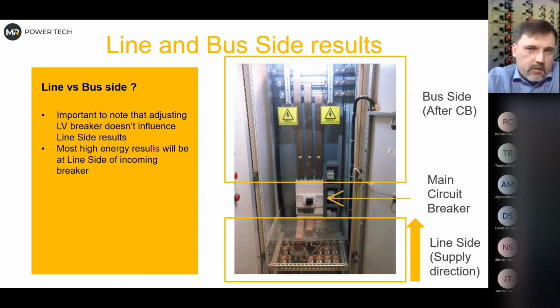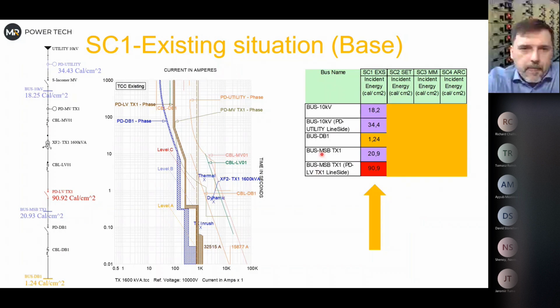There is one thing that I have to explain before we go further to the results: something which we call the concept between line and bus side. Just very briefly, because I think I explained it before. There is a cable connection, you see 7 cables per phase, and there is the outgoing and the main breaker. Everything up to here is protected by the medium voltage relay upstream. There is a main breaker, and everything after the breaker is protected by this breaker here. So we have a location inside the panel which is not really protected by this breaker. This is called line side or supply side or source side, depending on the software you are using. I use SKM for this one because it's a historical project, so we'll follow this one.